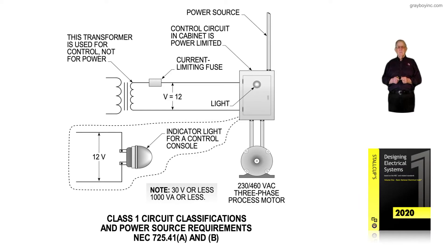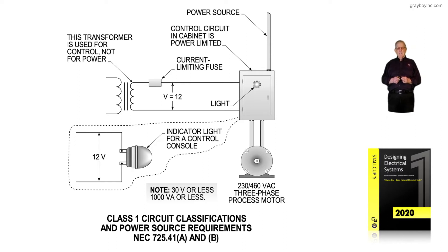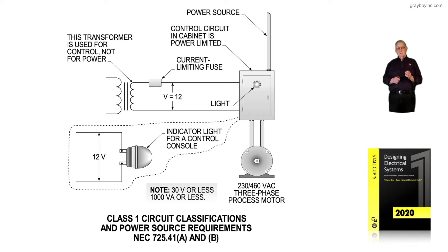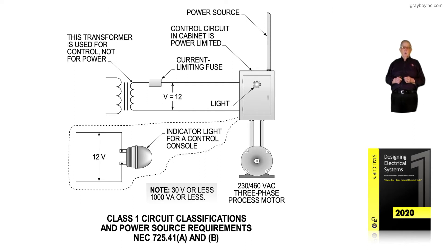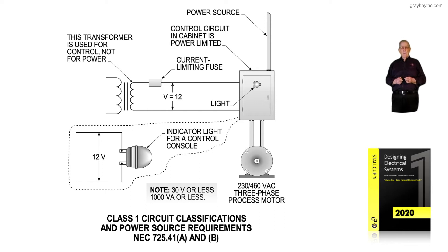This illustration deals with class 1 circuit classifications and power source requirements in accordance with NEC 725.41A and B. NEC 725.41A deals with unlimited power sources — voltages such as 120 volts, 208 volts, 240 volts, 480 volts, all the way up to 600 volts, which is how it was classified and used.